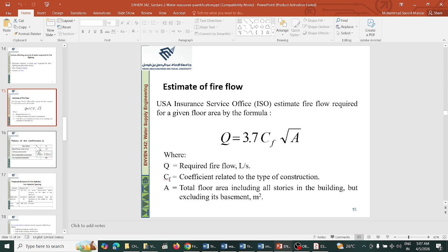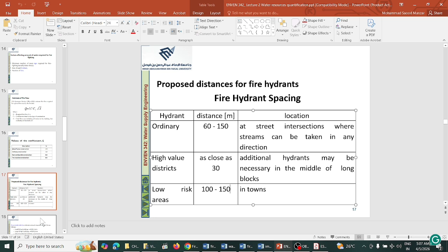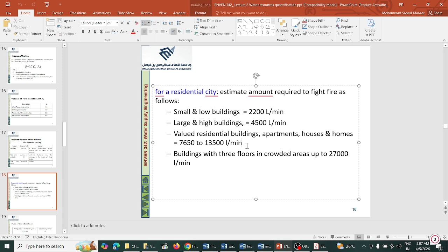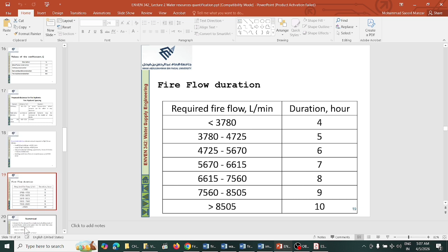Okay, now this is the distance of the hydrant. Ordinary is 60 to 150. For the high value it is lesser and for the low risk area it is more, and you can convert this particular value into liters per second also. So for small and low buildings it is lower, and for large and high buildings it is very high, and for valued residential buildings it is very high, and for buildings which have 3, 4, 5 floors, they will require more water. Okay, and this is the duration in hours. So if you increase the duration in hours, you will require more amount of water.